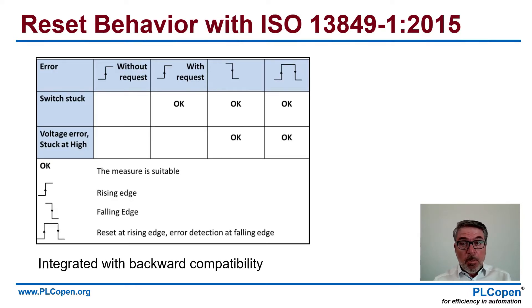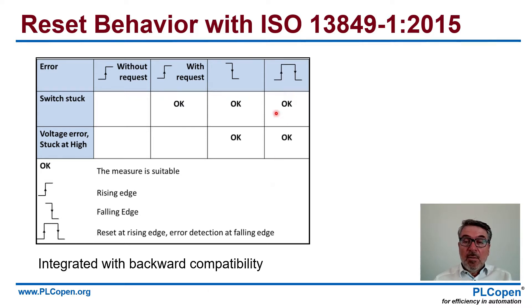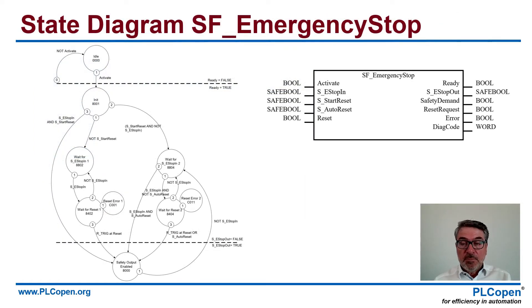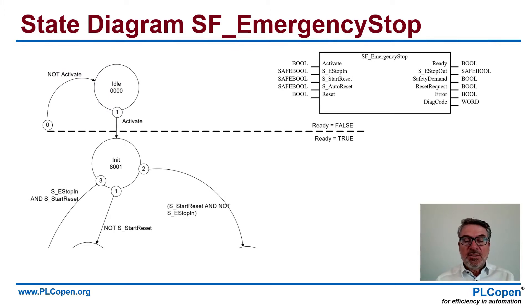This reset behavior is also compliant with ISO 13849, where you have in this case the rising edge and falling edge as the error detection part. Getting back to that, you see the function block here, with the start reset, auto reset, and reset as inputs, and of course the e-stop in. First of all, you activate the whole thing — this is what we do on top. We activate the function block and we get to state 8001.